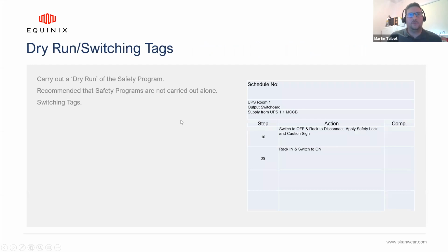You may wish to consider using switching tags. I always would recommend having a dry run. So once you've created your safety program, you do a pretend run of it to make sure that you've got everything correct, and all of your switching references are correct. And an extra level of safety is adding what we call a switching tag. So these are small parts of the safety program. For each individual switch or piece of equipment that you're going to operate as part of your safety program, you have a tag showing the steps that the operation carries out and the correct name and reference.